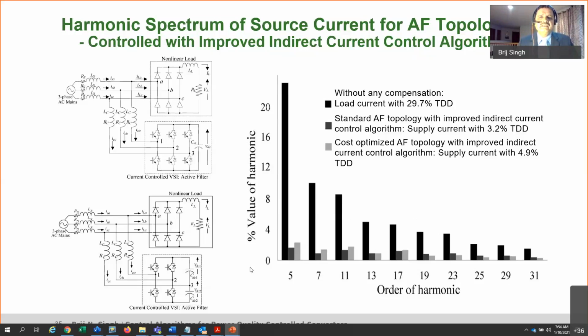Some people even developed filters for the 11th, 13th, and these first four dominant harmonics, 5th, 7th, 11th, 13th, leaving the rest in the neighborhood of 5%. So you could develop what you call a passive filter using LCR components. The problem is that if something changes in the load, it is very difficult to go and change it. Imagine a single phasing happened in your load, or somebody brought in a different type of load.